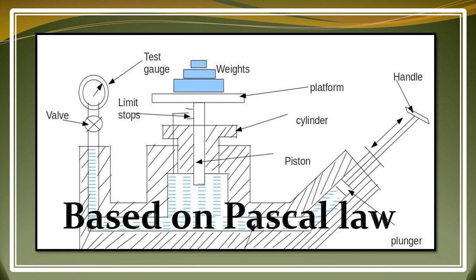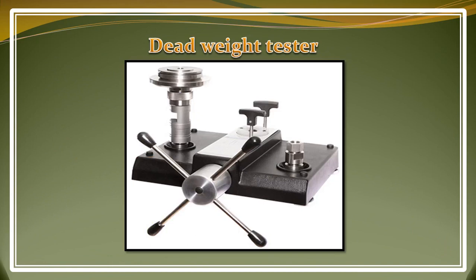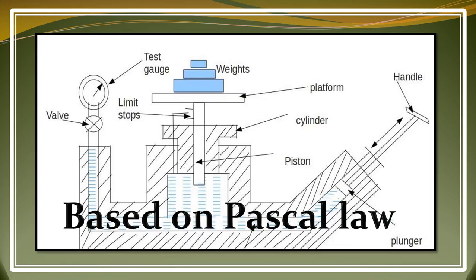As you can see in this image, actually this is a real deadweight tester. Actually this is a Bourdon deadweight tester, you can see. And in this image you can see a diagram which shows what is happening in this deadweight tester. As you can see, here is a valve, and this is a test gauge which is going to be calibrated by all this instrument. And here are weights. This is a limiter stop, and this is a cylinder. This is a piston, platform, handle, all the arrangement you can see.